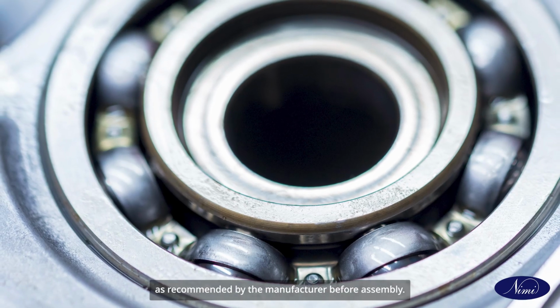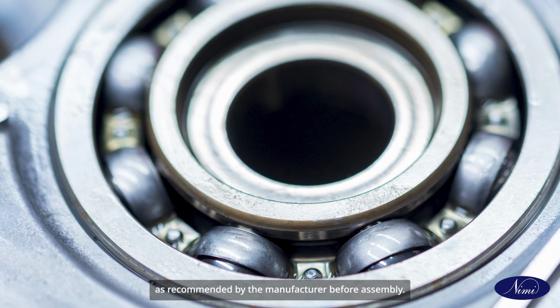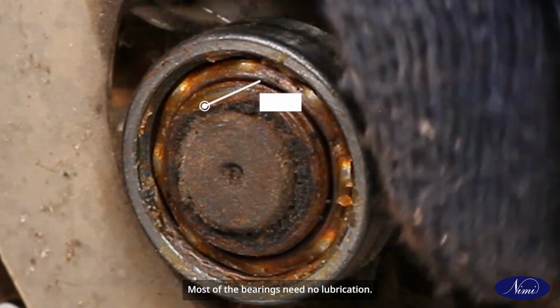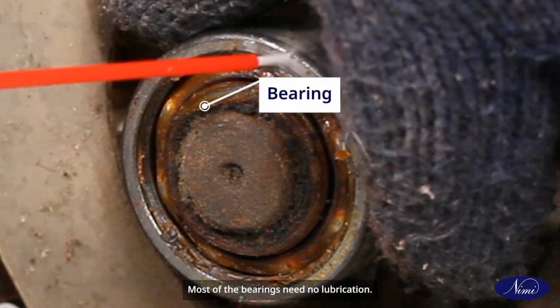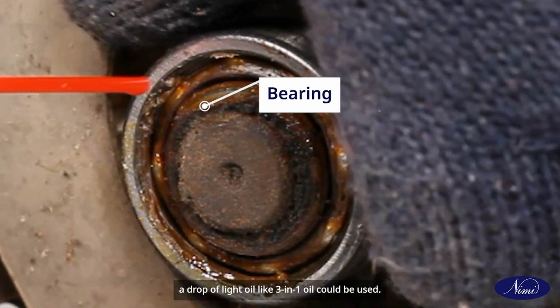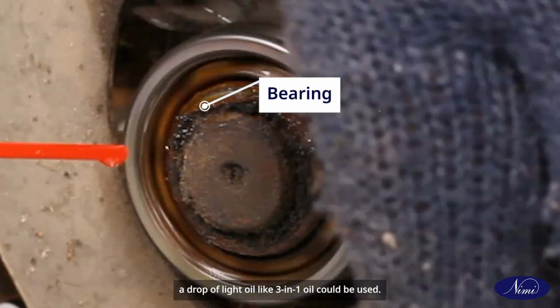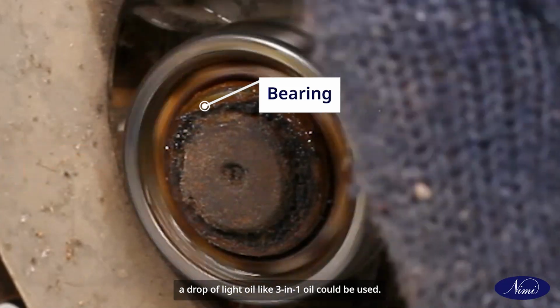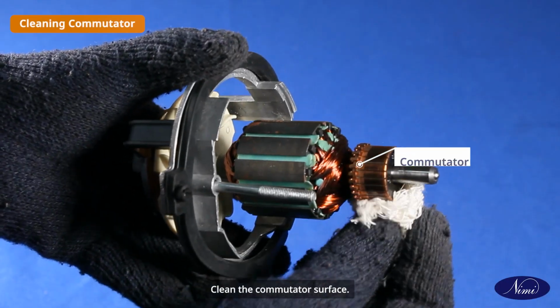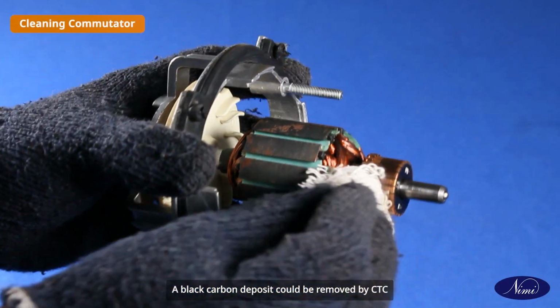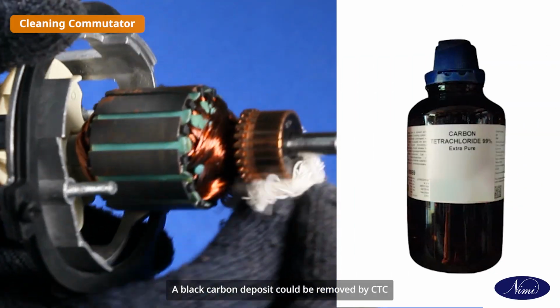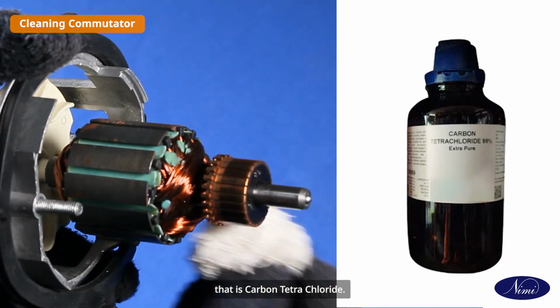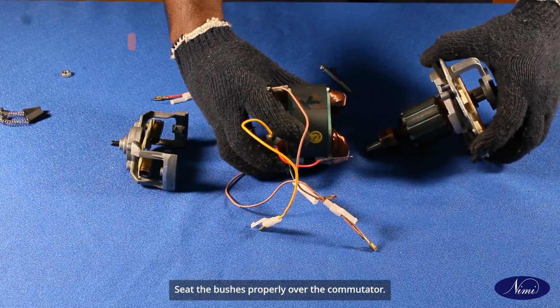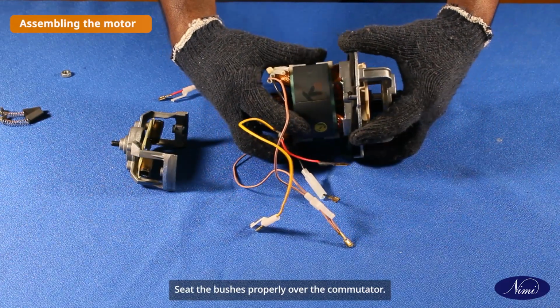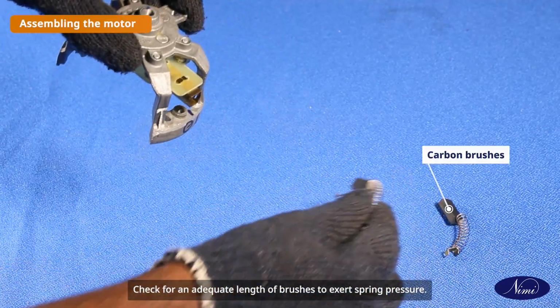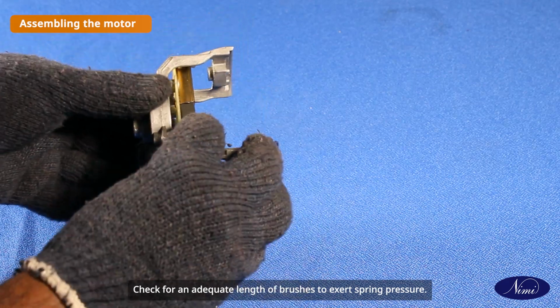Lubricate the bearing as recommended by the manufacturer before assembly. Most of the bearings need no lubrication. If required, a drop of light oil like 3-in-1 oil could be used. Clean the commutator surface. A black carbon deposit could be removed by CTC, that is, carbon tetrachloride. Seat the brushes properly over the commutator. Check for an adequate length of brushes to exert spring pressure.